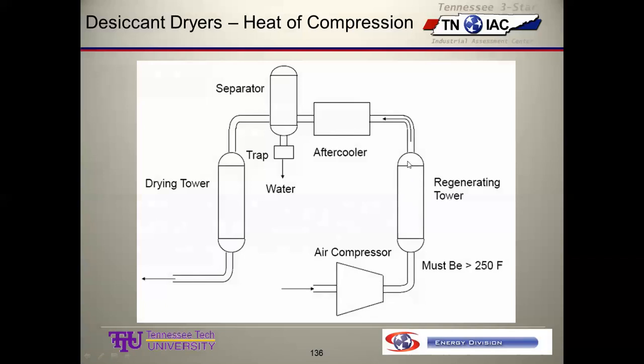And then we go here, so we strip out this moisture. Then we go to the after cooler, and it rains a boatload in there. So we take out not only the vast majority of the moisture that goes through the air compressor, we strip off the moisture in regenerating the tower, and then we have to condense all of that, or the vast majority of it, here. Then we put it through a separator and get the liquid water out of the separator through a trap, and then we go through the drying tower. And so it goes out. So we got our minus 40 dew point over here.